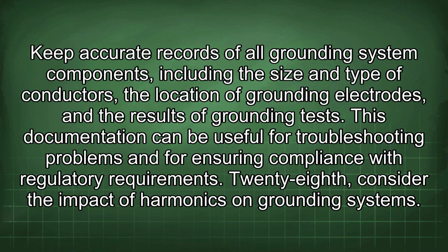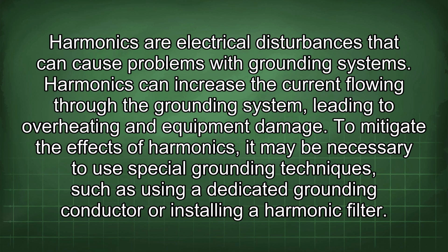28th, consider the impact of harmonics on grounding systems. Harmonics are electrical disturbances that can cause problems with grounding systems. Harmonics can increase the current flowing through the grounding system, leading to overheating and equipment damage. To mitigate the effects of harmonics, it may be necessary to use special grounding techniques, such as using a dedicated grounding conductor or installing a harmonic filter.